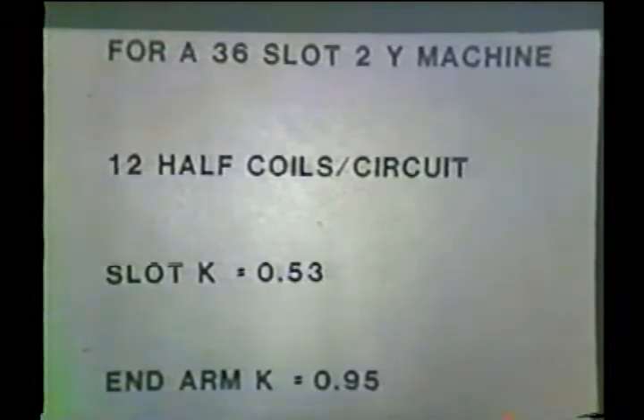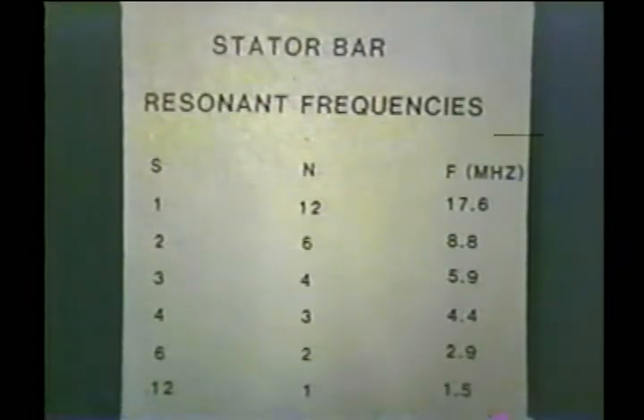For the one particular machine that I showed you a curve of earlier, the 36-slot 2Y machine, 907 MVA, there were 12 half coils per circuit. The velocity constant in the slot was 0.53, and the velocity constant in the end arm was 0.95. By using the previous equations and calculating out these frequencies, we can develop several frequencies at which oscillations may occur.